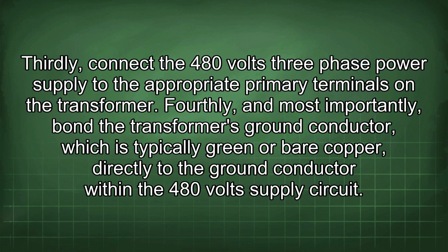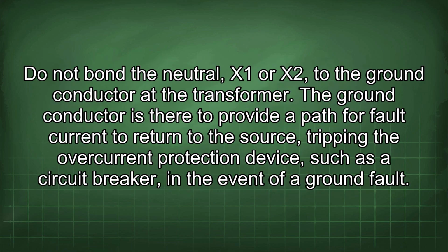Fourthly, and most importantly, bond the transformer's ground conductor, which is typically green or bare copper, directly to the ground conductor within the 480 volts supply circuit. Do not bond the neutral, X0 or X2, to the ground conductor at the transformer. The ground conductor is there to provide a path for fault current to return to the source, tripping the overcurrent protection device, such as a circuit breaker, in the event of a ground fault.